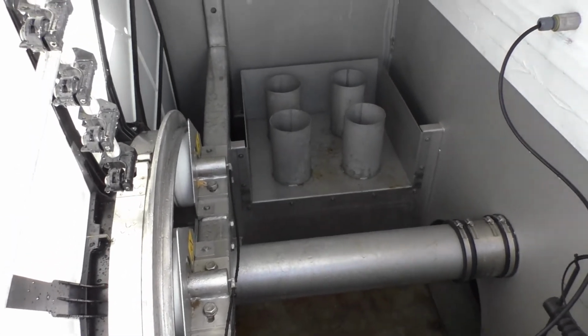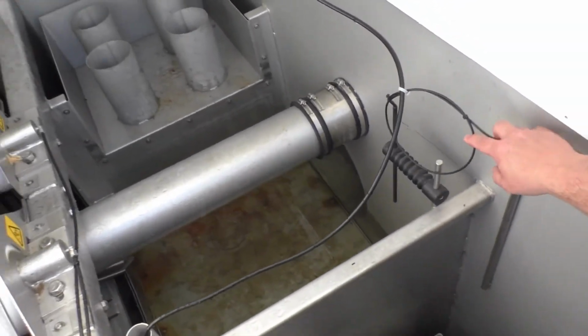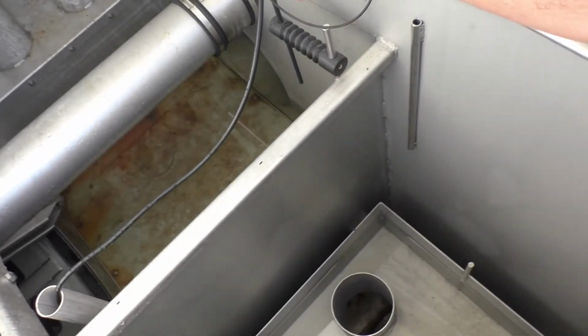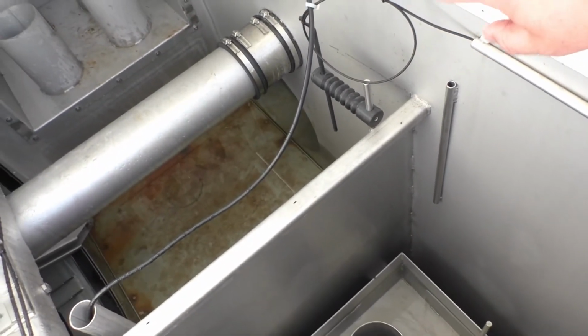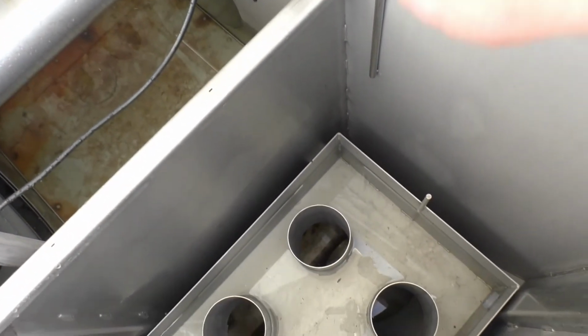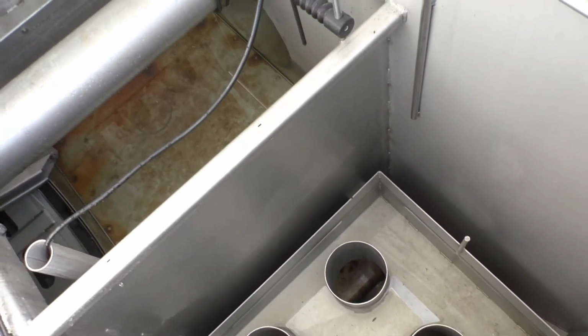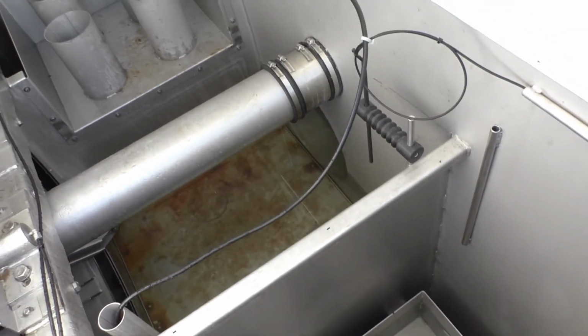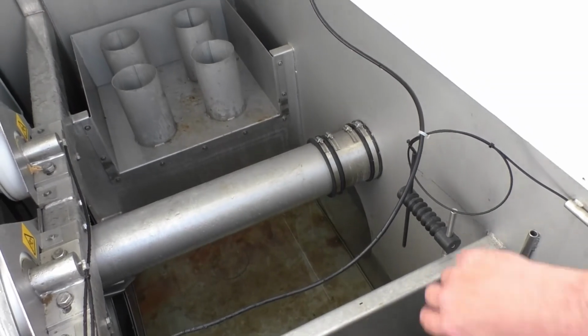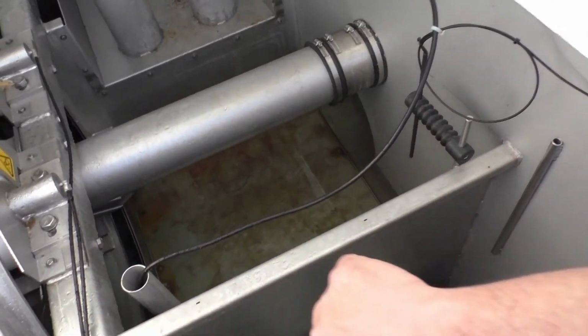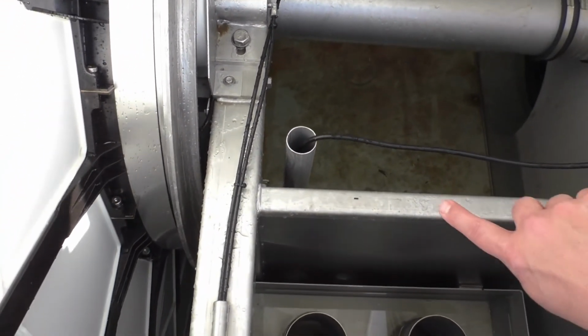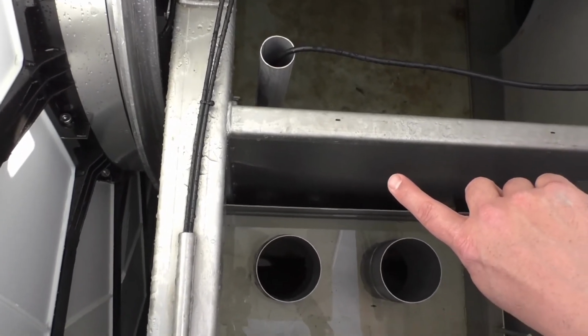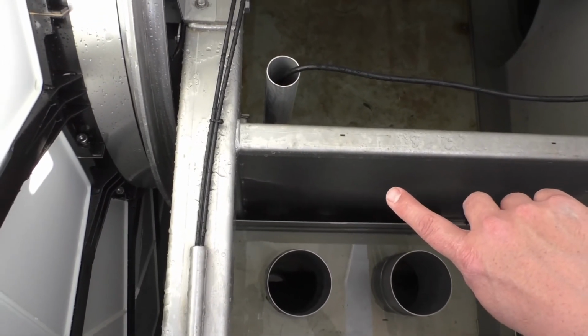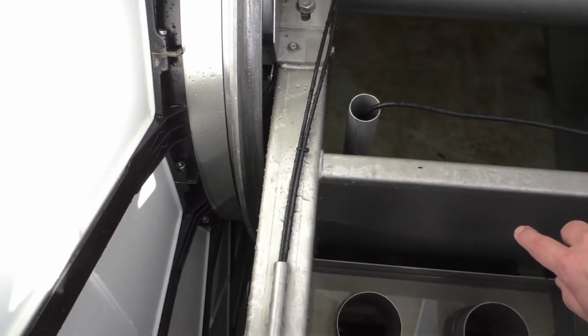Your probe right here that you see, this is your high level probe. The bottom of it is set 1.5 inches below the overflow box over there to give you an alarm. And we try, it's 1.5 inches to at least try to give you a heads up if you're in a high flow situation. This cable here that goes into the stilling well, that is a pressure transducer. That is what determines when the water level is 8 to 9 inches above your effluent weir.